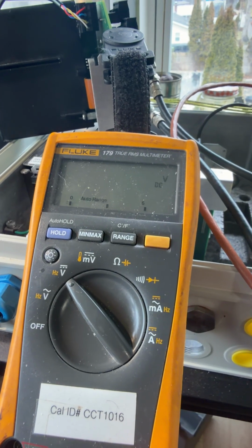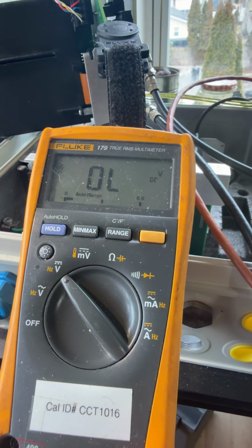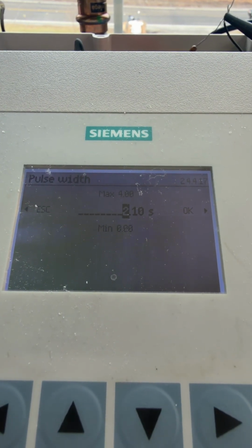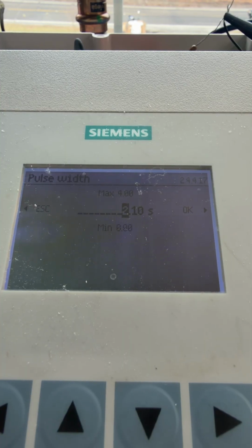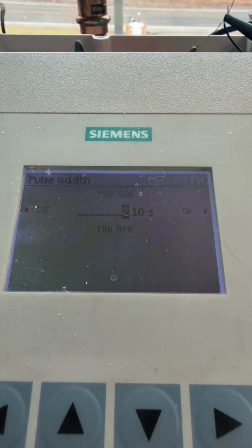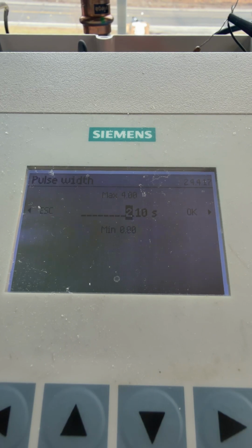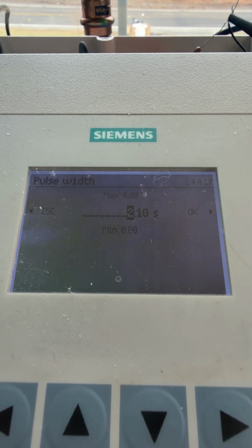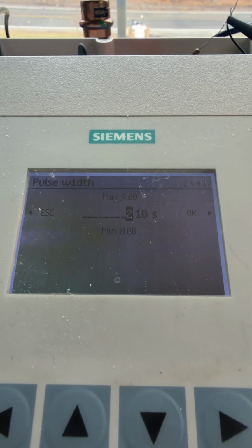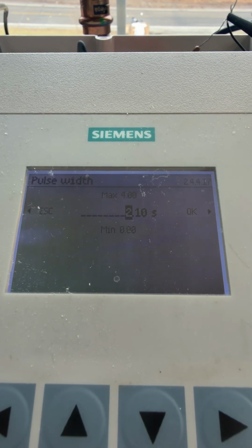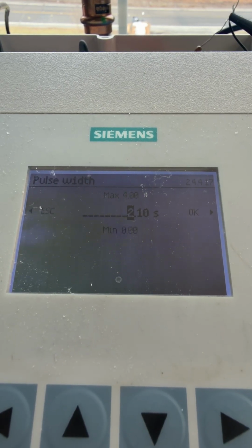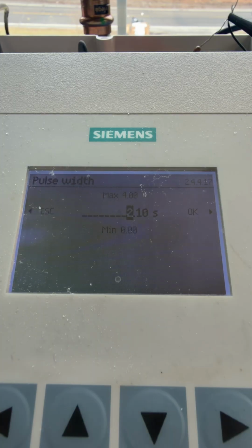Just remember, when you're done with your test, you're going to want to go back and set your pulse width narrow enough so that if your frequency gets pretty high, your pulse width is not staying on too long. Otherwise, each one pulse width will run into the next pulse width. So you can set that to as low as your PLC or whatever you're hooking up to the meter will be able to still capture.